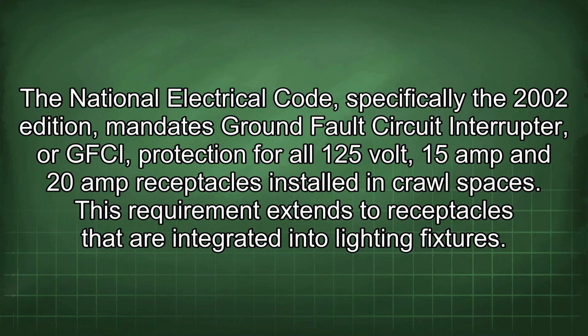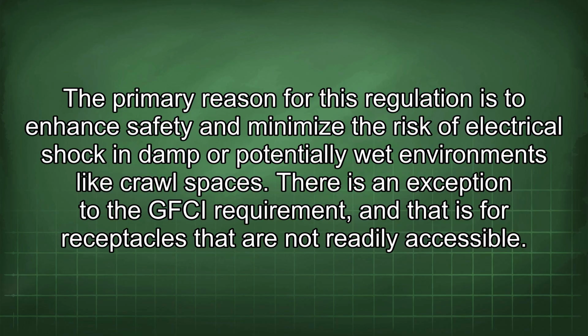The National Electrical Code, specifically the 2002 edition, mandates ground fault circuit interrupter, or GFCI, protection for all 125-volt, 15-amp and 20-amp receptacles installed in crawl spaces. This requirement extends to receptacles that are integrated into lighting fixtures. The primary reason for this regulation is to enhance safety and minimize the risk of electrical shock in damp or potentially wet environments like crawl spaces.